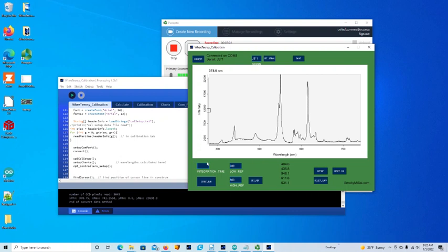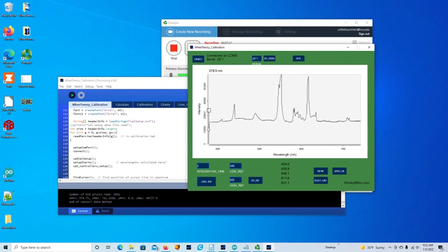Okay, so let's put a 2 in there again, hit the start run. And let's see, 1,000, 2,000, 3,000, 4,000, that's less than 5,000 counts, right? So we want to change this high reference number so that when we max it out, it'll be at 65,000.